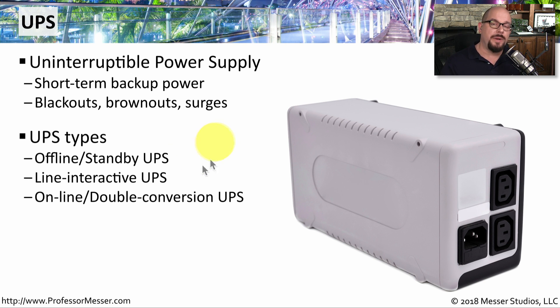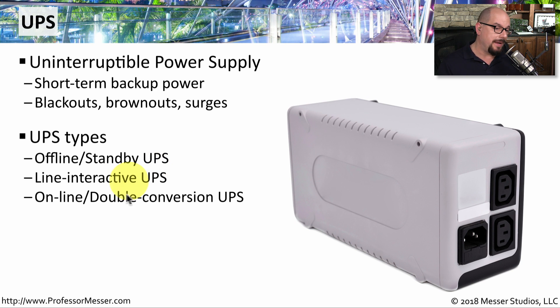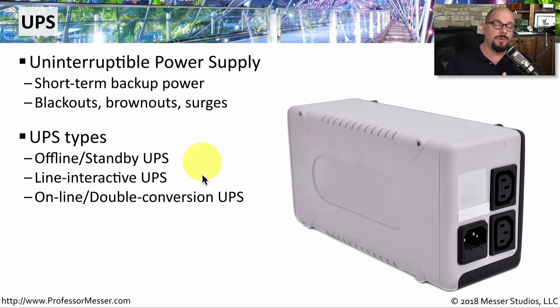There are generally three categories of UPS. One is an offline or standby UPS that will only switch over to battery if you lose the main power source. There's also a line interactive UPS that can slowly bring the power up from the battery, which is very useful if you happen to have a brownout.